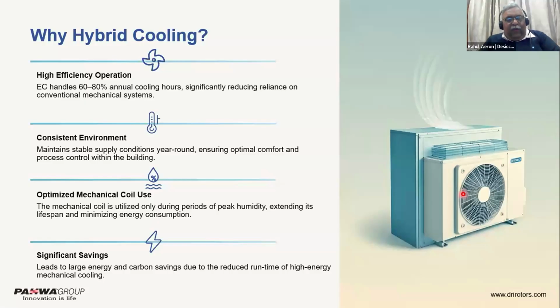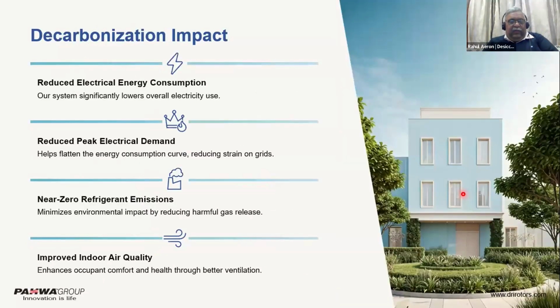So hybrid cooling saves a lot of energy. It can be used year round, even in hot and humid climates. We optimize our mechanical cooling usage. So we use the refrigeration system or the mechanical cooling system only when the humidity is high, and it can offer very significant savings for us. So that's where I would like to end my presentation.